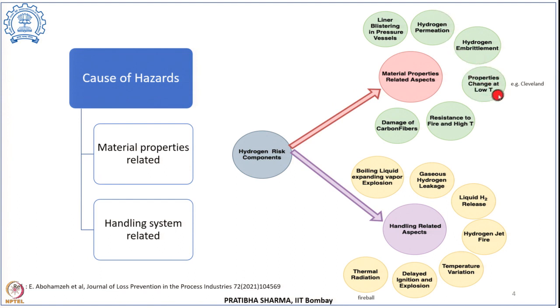Another material property related hazard is the change in properties at low or cryogenic temperatures. When materials such as containment vessels or pipelines are subjected to liquid hydrogen or low-temperature hydrogen, there is a change in their mechanical properties. At low temperatures, there could be a change from ductile to brittle behavior, unexpected plastic deformations, or a phase transformation resulting in a change in the elastic and mechanical properties. There could also be thermal contraction of the materials, which varies from material to material.